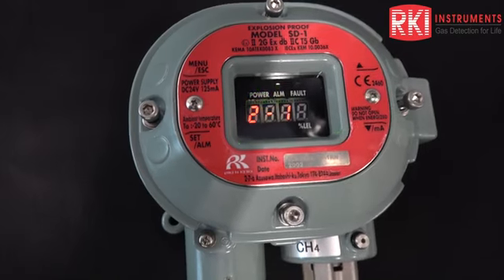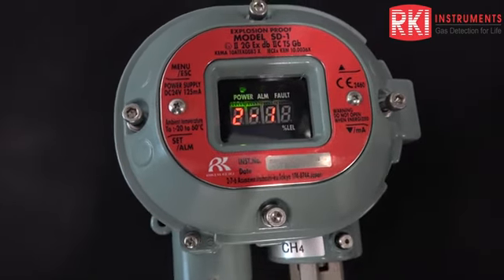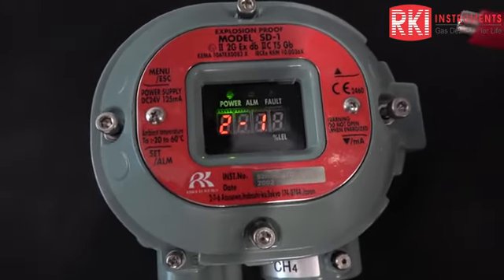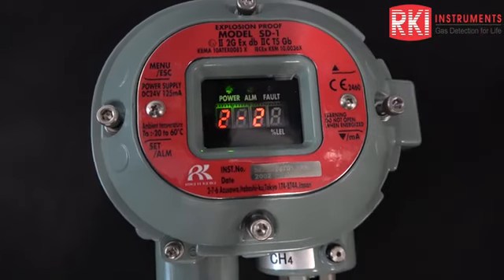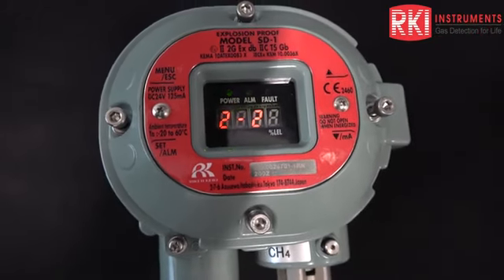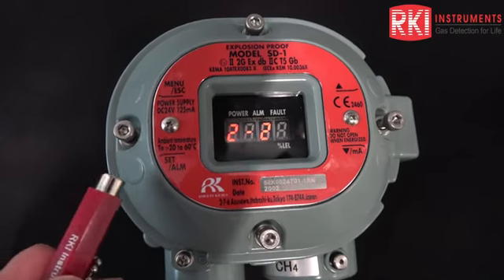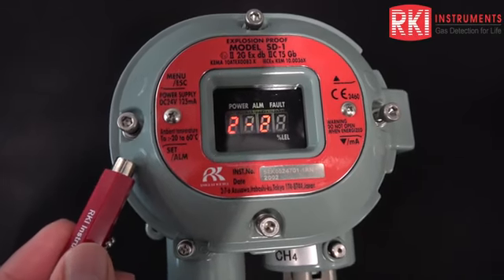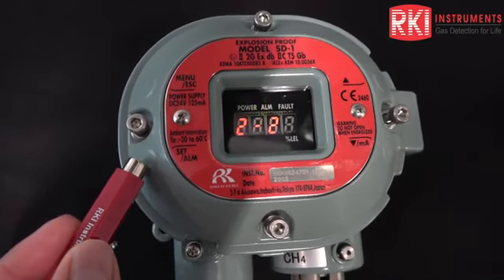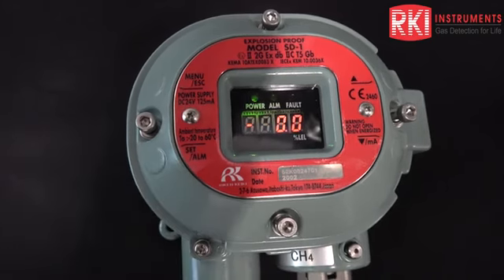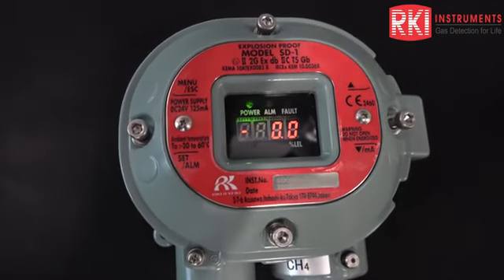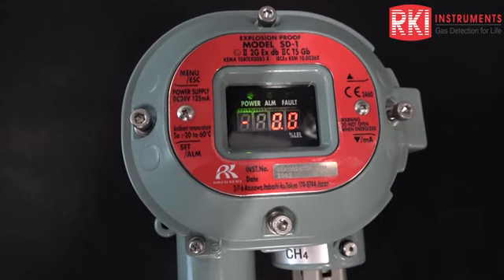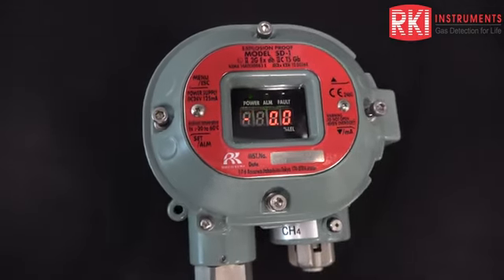And now I want to put some span gas to it. So now I want to take the up value pad to 2-2, and that is the calibration level. So once again, I'm going to go over to the set pad. Just hold my magnet there for a moment. Okay, and I'm at 0 basically. So at this point, I can put the cal gas to it, which is what we're going to do.